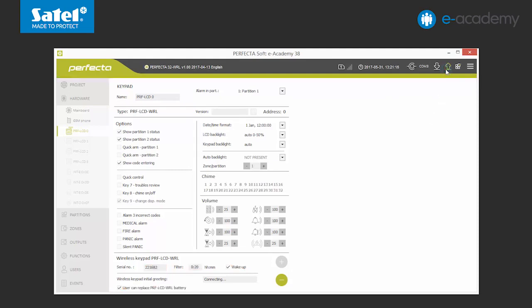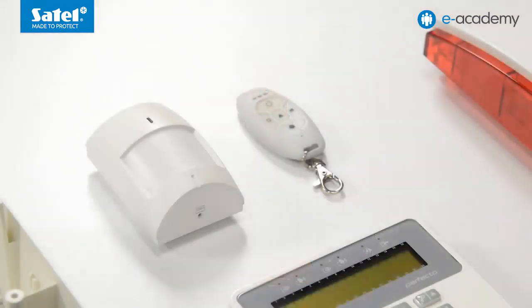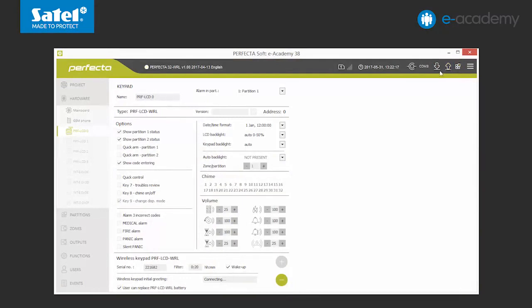We send the data to the control panel. Now we will show you the second automatic way of adding a wireless device to the Perfecta system. It may be useful when it is impossible to check the serial number. We will show you this method on the example of the MPD300 detector. So let's move on to the zone tab.